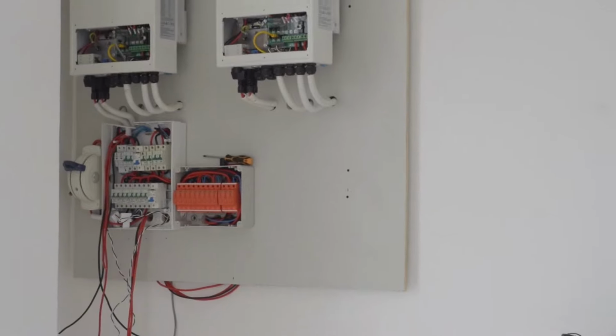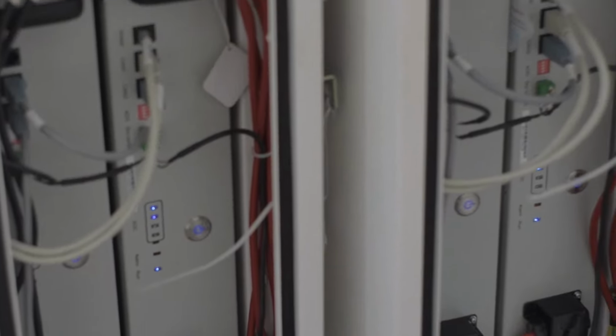Okay, first I need to start from the size of the system here. He has a 10 kVA inverter capacity, and that determines the maximum load you can have on the system. He also has a 19.2 kilowatt hour lithium-ion battery bank—in layman's terms, like a 400 amp, 48 volt battery bank capacity. When buying regular AGM batteries you'd ask for 200 amp, 12 volt batteries, but this is a 400 amp, 48 volt lithium-ion battery bank, plus a 13 kilowatt solar panel array. That's what he has on this property.